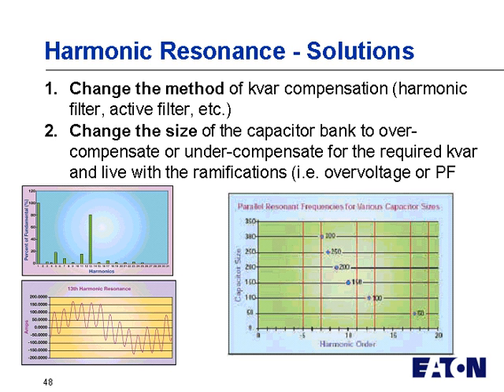Now, the bottom left-hand picture shows harmonic resonance near the 13th harmonic, which really, if you look, the waveform that's in the background is a superimposed 13th harmonic on top of a 60 hertz. On the right, what we show are the red lines vertically show the harmonic resonances or the harmonic sources that are available in the system, like 5th, 7th, 11th, 13th, for example, and it's showing different sizes of capacitor banks. So as you approach one of those red lines, you could have an issue.